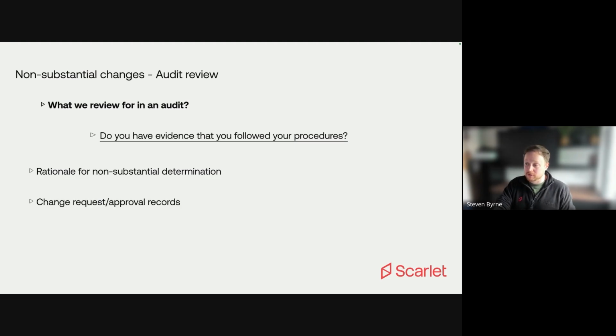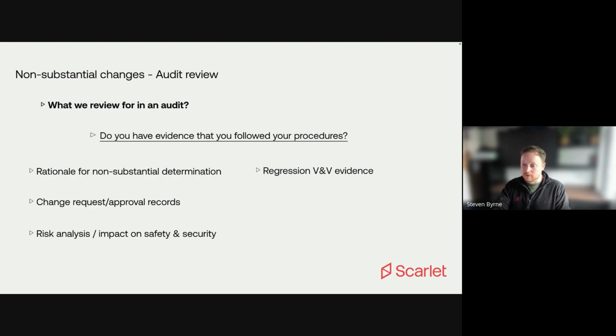We want to see the change records, so where it's being requested, the review and approval process for that, and then the documentation that's gone with every change. That's really more from a QM perspective. Are you following a proper change request and approval process? We want to see if your risk management has been updated. Have you incorporated the new changes and considered the impact on safety and performance? If there was any testing required for changes, you should be able to pull up the regression test evidence for that. As well as that, your software configuration management, being able to see the control changes within your Git repo or wherever you're storing your software.